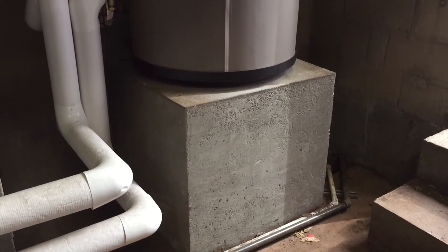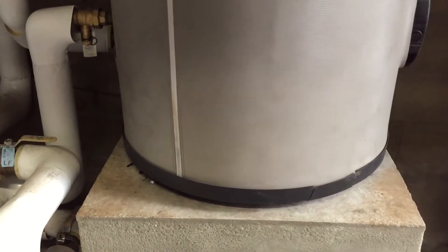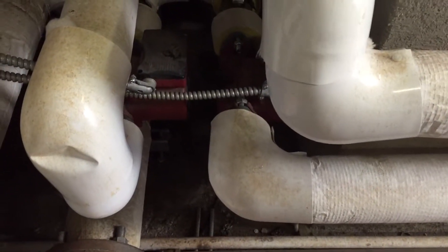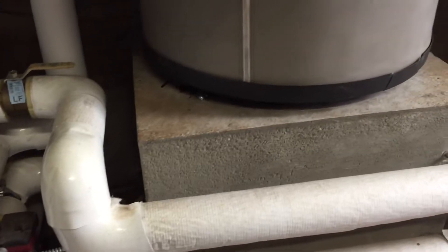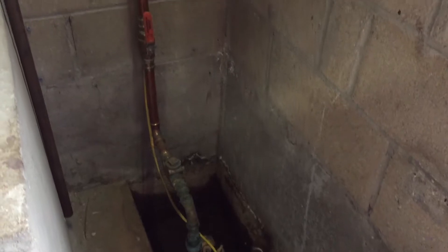They're raised quite high because the previous water heaters were flooded, so we had to raise them above the flood level. We have these reddish fittings over there — those are circulators serving the domestic hot water heaters, or indirect water heaters. And here we have a sump pump. We always install pits with a sump pump. This is the drain line.